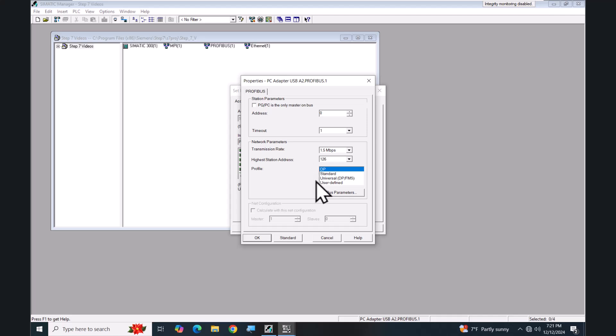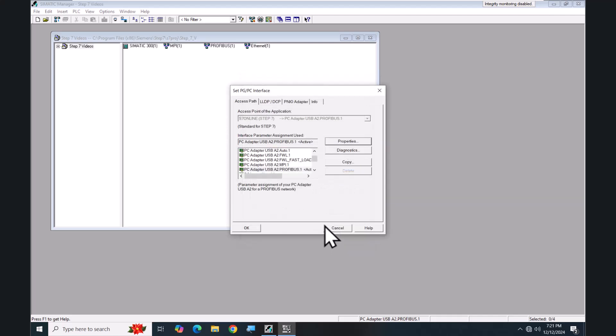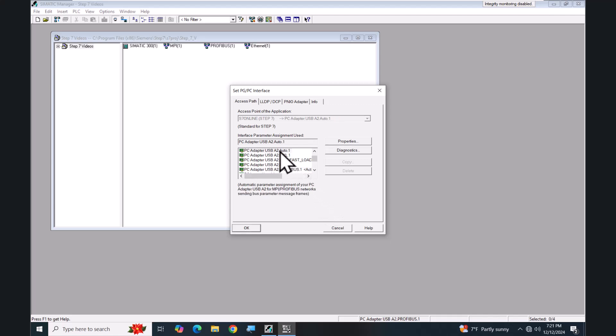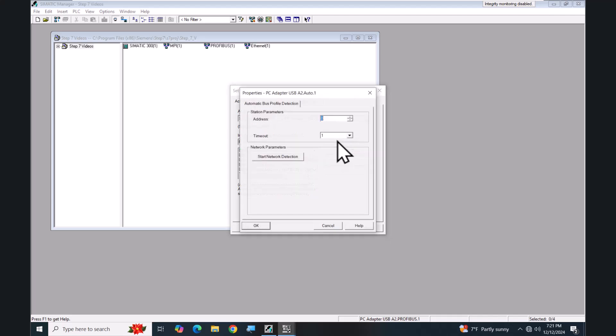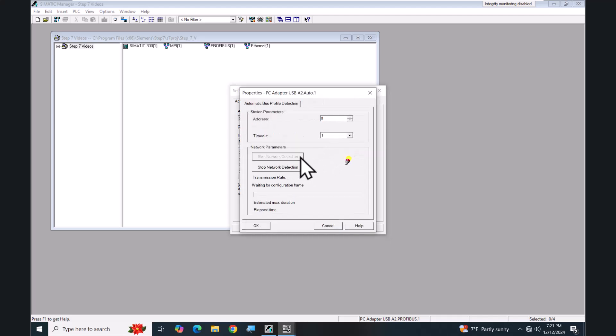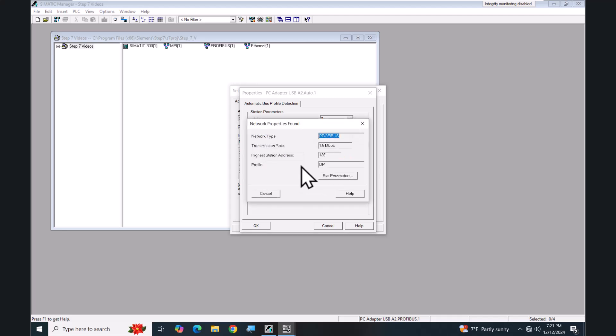If you don't know the parameters for your PROFIBUS network, you can select the auto connection. So now I'm using the PC Adapter USB A2 in the auto mode. I can select the properties and then you can start a network detection. This goes out and finds the current bus parameters for your network.